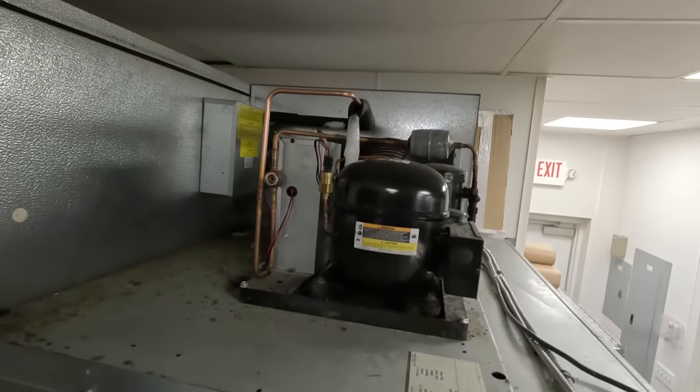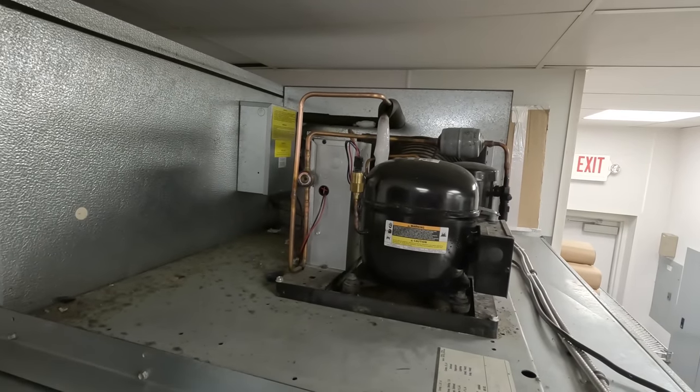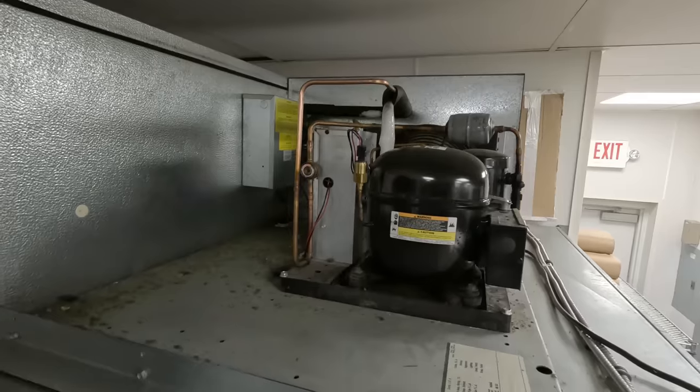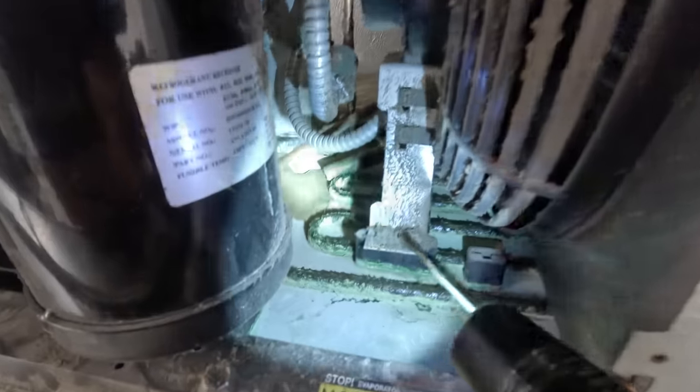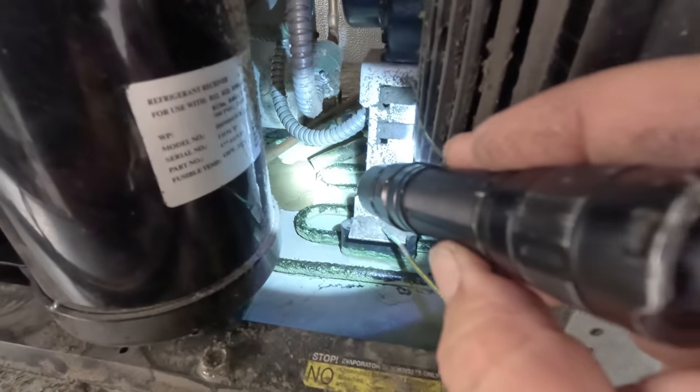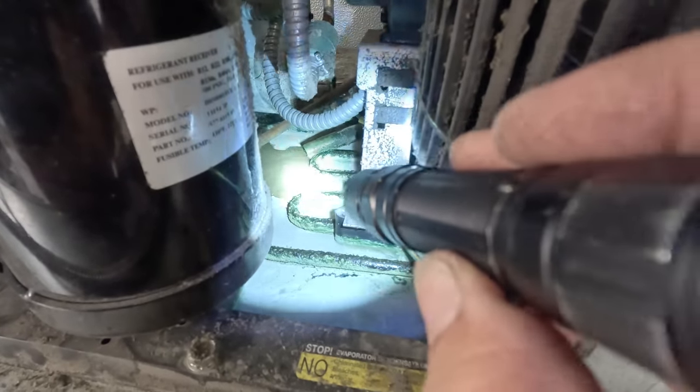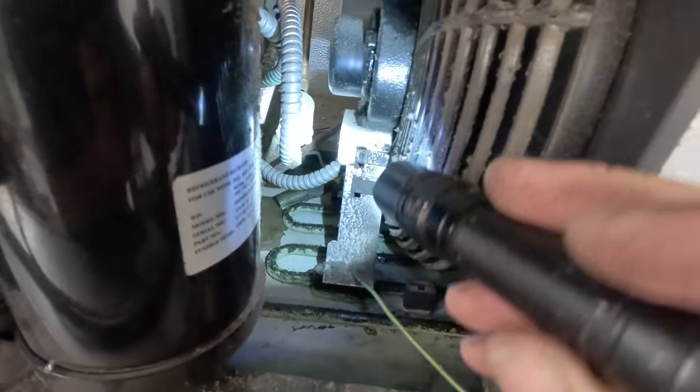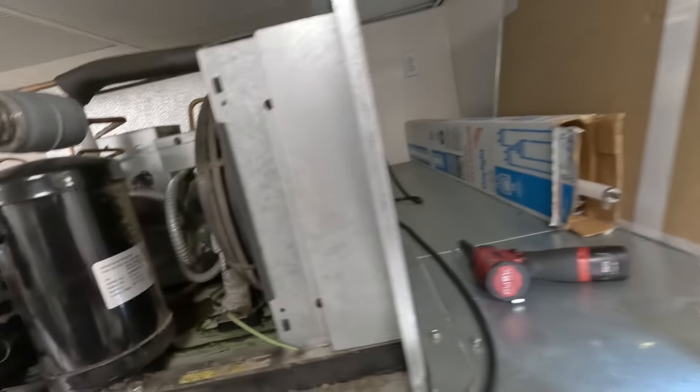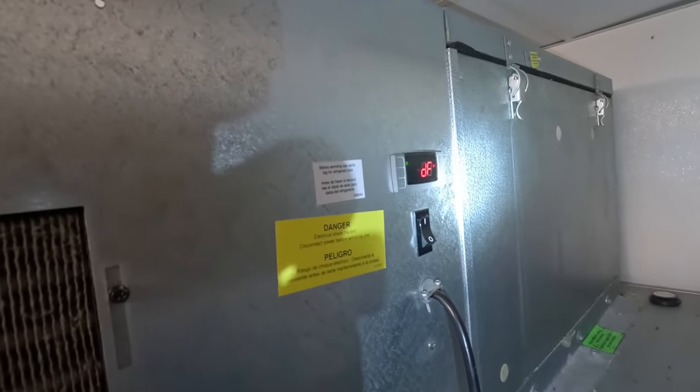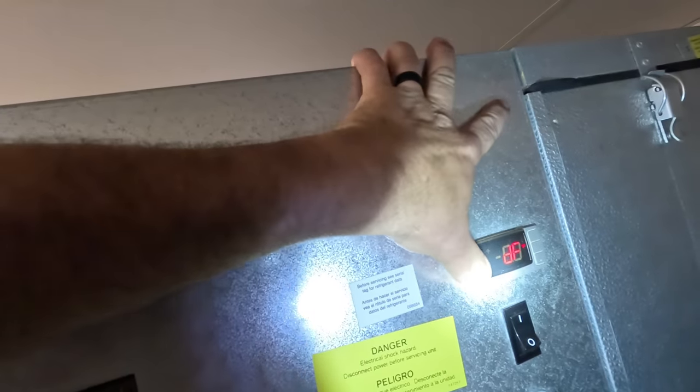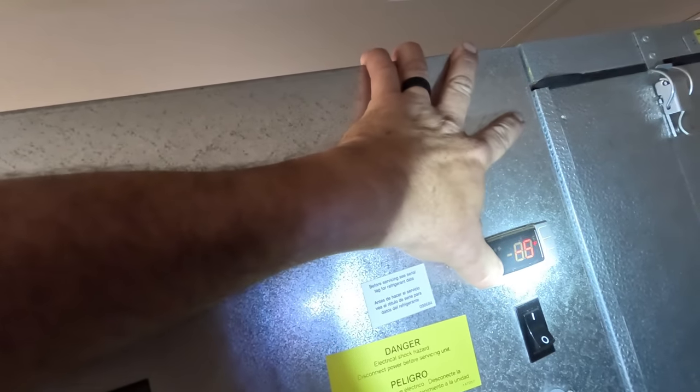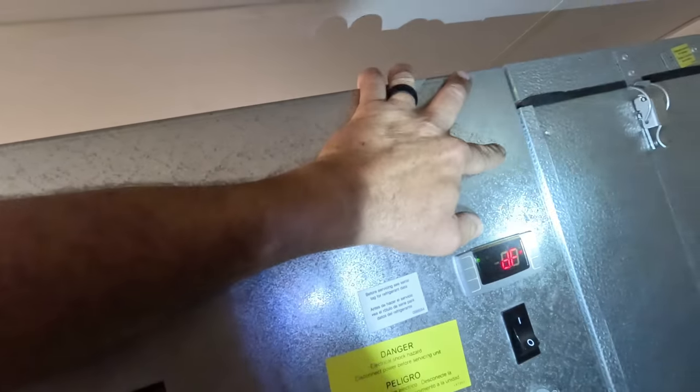Let's find out why it's not defrosting. Is it a heater? Is it a relay? Is it the controller? Is it the termination switch? Is it the suction transducer? What's causing it? Looking for some clues here. If you look at the water in the pan, it makes you think it's probably trying to defrost. Otherwise, how would you get water in there? So that makes me wonder if the compressor is sticking on, which makes me think the control there may not be sensing temperature correctly. It's set for negative five. I think it's in defrost now and it's sticking on. That's what I think's going on.